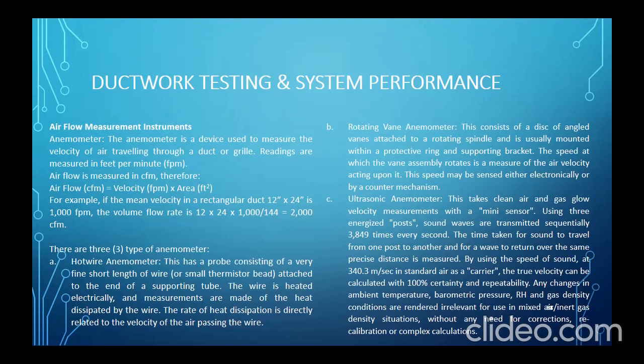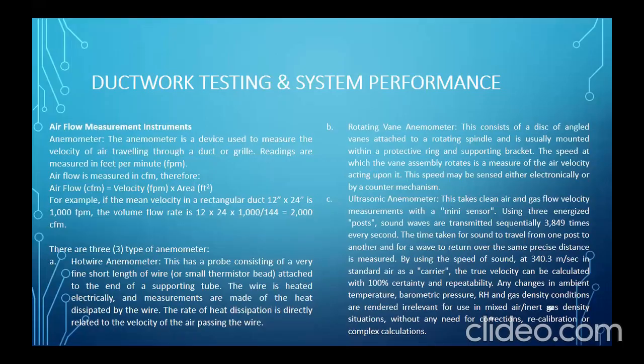This takes clean air and gas flow velocity measurement with a mini sensor. So using three energized posts, sound waves are transmitted sequentially at 3,849 times every second. The time taken for sound to travel from one post to another and for a wave to return over the same precise distance is measured. By using the speed of sound at 340.3 meters per second in standard air as a carrier, the true velocity can be calculated with 100% certainty and repeatability. Any changes in ambient temperature, barometric pressure, and gas density conditions are rendered irrelevant for use in mixed air or inert gas density situations, without any need for correction, recalibration, or complex calculation.